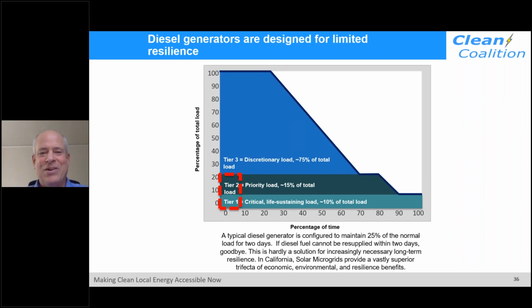I'm running out of time, so I'll go a bit quickly. I want to make the point that diesel generators are not resilient, for a lot of the reasons that came up in Mike's and Jana's presentations. Diesel has a limited lifetime—the typical diesel generator has 2 days of fuel supply on hand. The resilience you get from a typical diesel generator is shown in this red hatched rectangle in the diagram, meaning you keep 25% of the load on. Diesels are typically sized for tier 1 and tier 2 loads, and keep them on for 2 days—that's your standard diesel generator configuration. It's a very small percentage of the overall resilience compared to a solar microgrid, as you can easily see from this diagram.